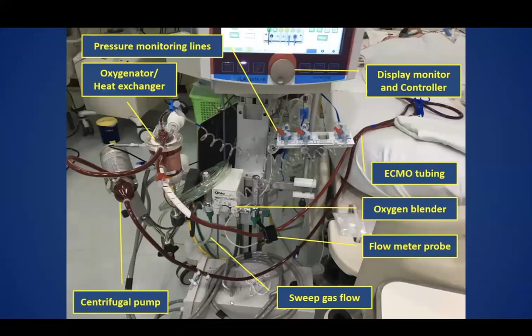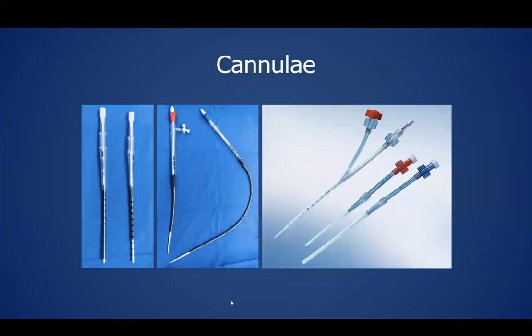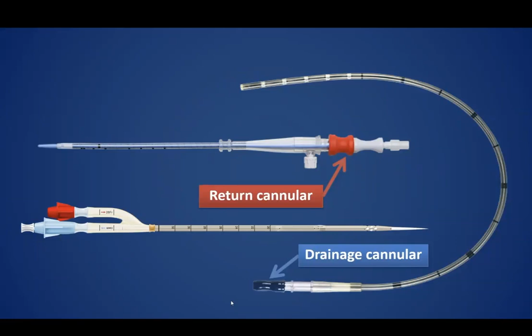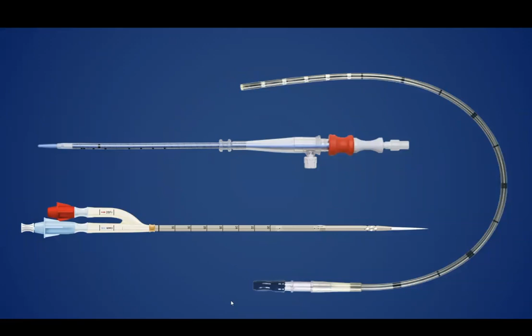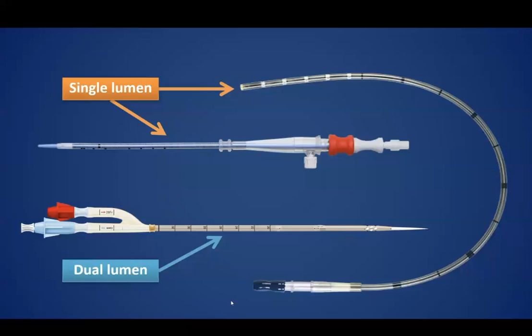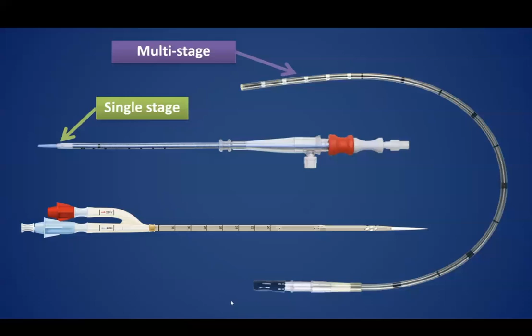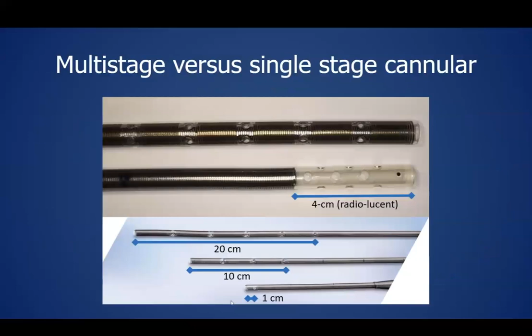More detail about individual ECMO components. The cannula is the interface that connects the ECMO to the patient's cardiovascular system. The drainage cannula is usually coated in blue, and the return is usually coated in red. The dual lumen cannula is used only for VV ECMO. The multi-stage cannula is available for larger patients. The care team should know the tip characteristics and visibility on X-ray because the tip position will determine the circuit flow.